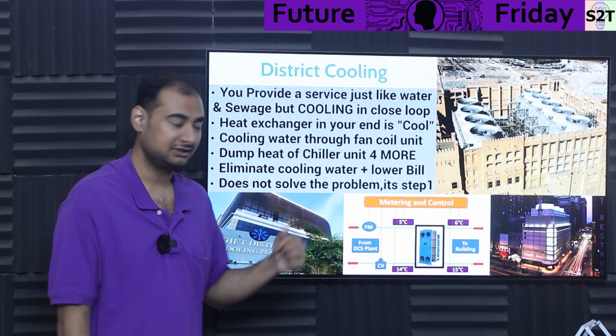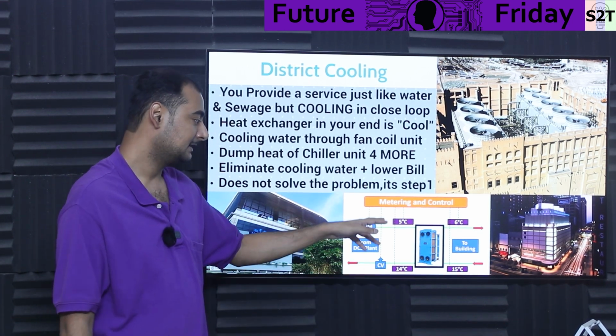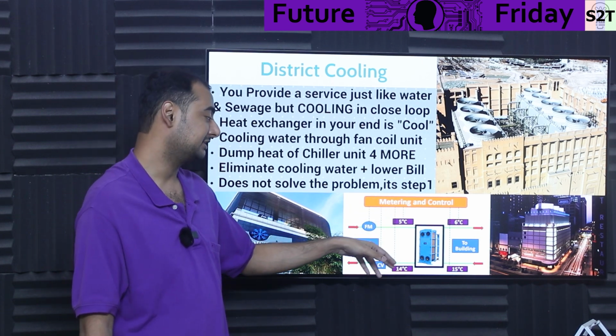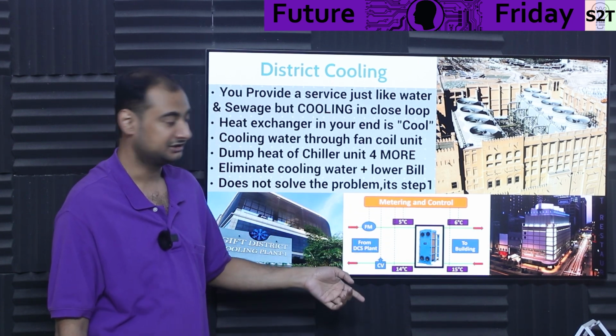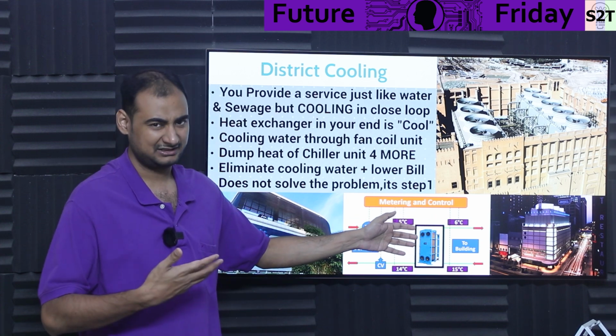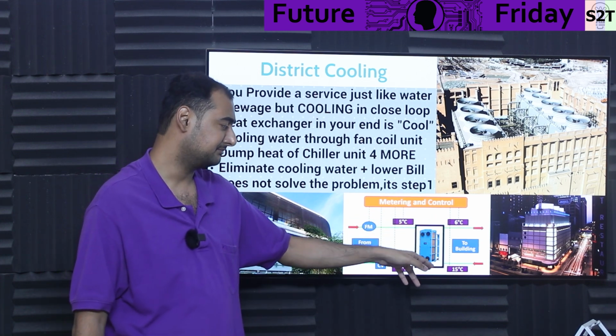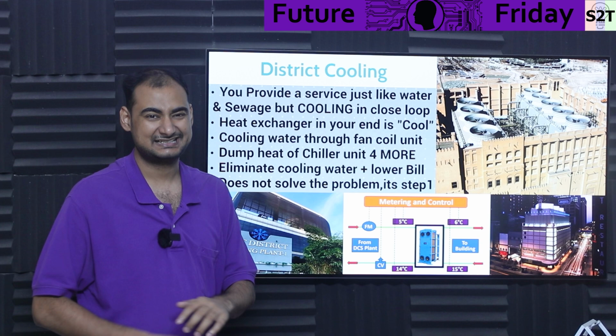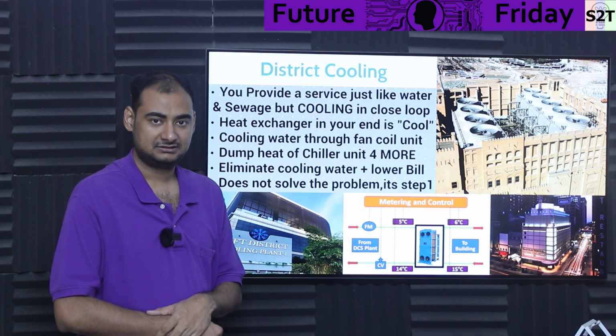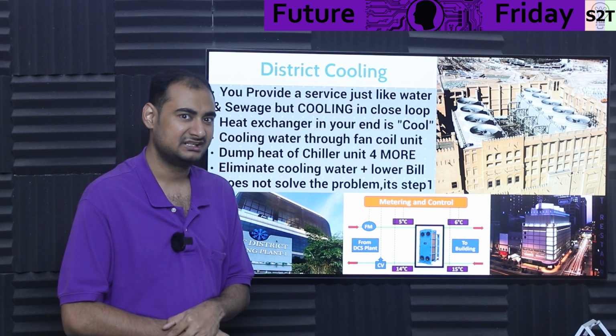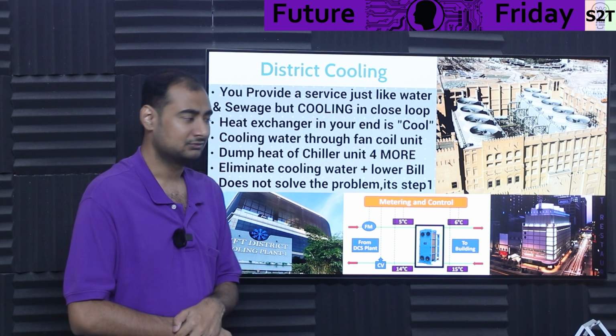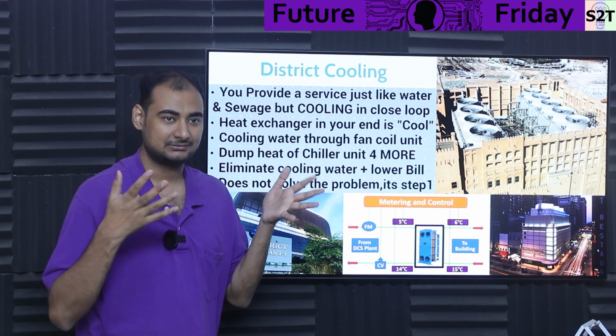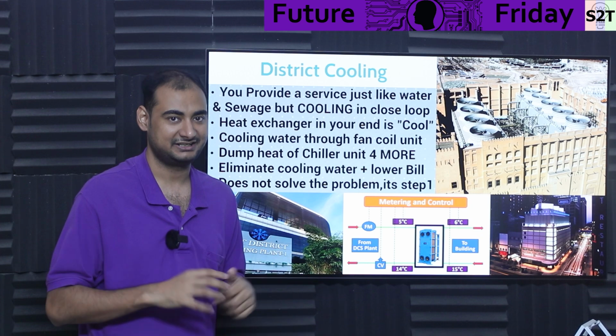Another benefit is a lower bill. Why? Well, this is an Indian system where coolant comes in at 5 degrees Celsius and leaves at 14 degrees Celsius, using a plate heat exchanger, which is fairly efficient. So you dump 15 degrees Celsius and extract 6 degrees Celsius. That's cooler than what you'd generally want, even in a server room. So what does that translate to? It means your compressor is working in a positive delta, not a negative delta.